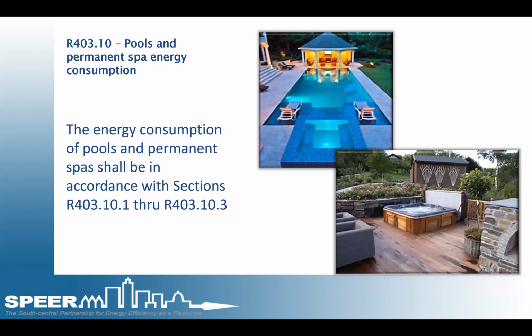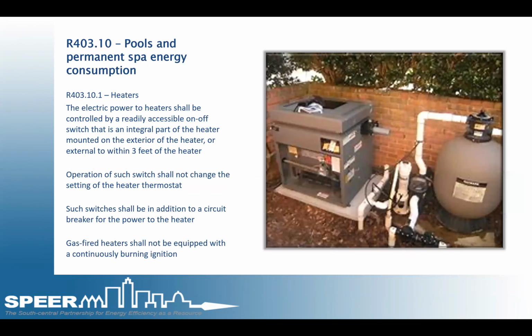Pools and permanent spas. The energy consumption for pools and permanent spas has to be in accordance with sections 403.10.1 through 403.10.3, which we'll go through right now. Point 1 is the heaters. The electrical power to the heaters shall be controlled by a readily accessible on-off switch that is an integral part of the heater, mounted on the exterior of the heater or externally within 3 feet of the heater. Operation of those switches shall not change the setting of the thermostat. Such switches are in addition to the circuit breaker from the house power to the heater. Gas-fired heaters should not have continuously burning ignition pilot systems.